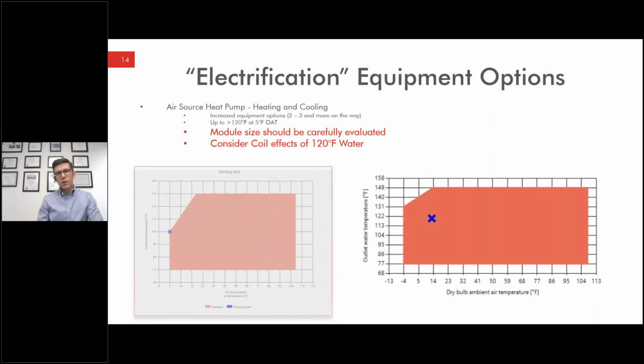The other note here is the coil. Obviously with lower temperature water, and often a lower delta T than you might have experienced with older fossil fuel burning systems, you've got to think about how you're selecting coils. It's not the same coil you would have selected for 180, 150. So be mindful of that. Often that's an achievable thing. It's not something you have to worry about. You just have to make sure you're selecting the right coil.